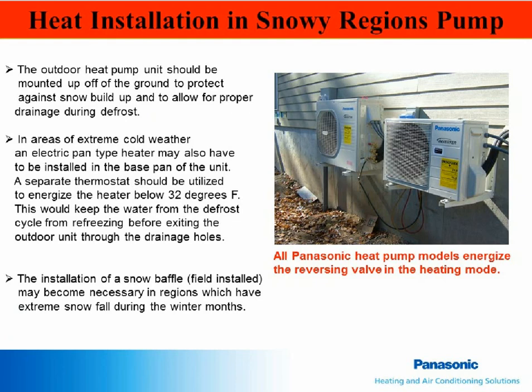A drain connection can be attached at the bottom of the unit, but it is possible that the drain itself could freeze and clog if heat tape is not used. The coils themselves could defrost and be clear while there is still ice buildup in the pan. If air temperatures are below freezing, this ice buildup could grow until it strikes the fan.